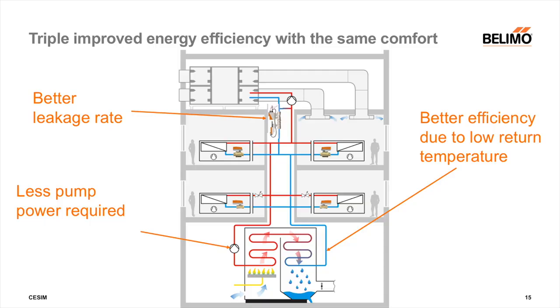In summary, with the Belimo energy valve you can achieve a triple improvement in energy efficiency with the same comfort. With only this one valve, it is possible to have an influence at three points in a building: a better leakage rate reduces the energy flow; reducing the differential pressure leads to less pump power; and higher efficiency at the boiler is achieved through delta-T management.